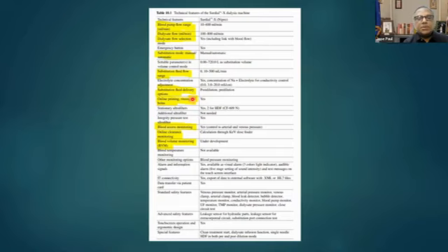Substitution fluid delivery can be post-dilution or pre-dilution. You can use online priming, rinsing, and IV bolus. Everything can be done automated by the machine. There is an option for blood access monitoring, and there is online clearance monitoring. These are in general the technical features of the machine. As dialysis personnel, you will be interested in all these technical details.